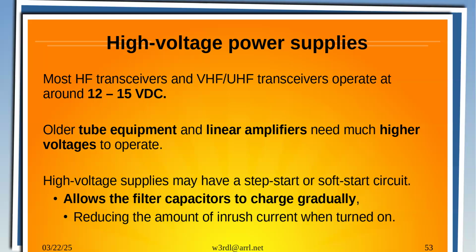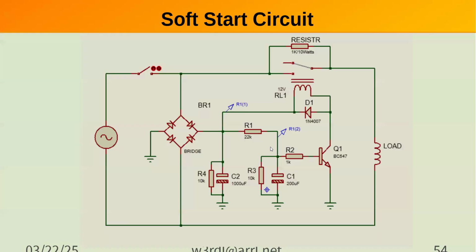So when you first turn it on and you've got these giant filter capacitors that look like a short circuit, it blows your fuse unless you do something like that. So you need something to allow the filter capacitors to charge more slowly, have less surge current, or inrush current as they call it. This is a typical circuit, and a lot of them will have a relay.